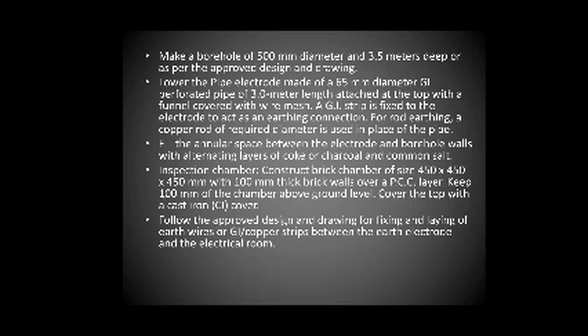Inspection chamber. Construct a brick chamber of size 450 x 450 x 450 mm with 100 mm thick brick walls over a PCC layer. Keep 100 mm of the chamber above ground level. Cover the top with a cast iron cover. Follow the approved design and drawing for fixing and laying of earth wires or GI copper strips between the earth electrode and the electrical room.